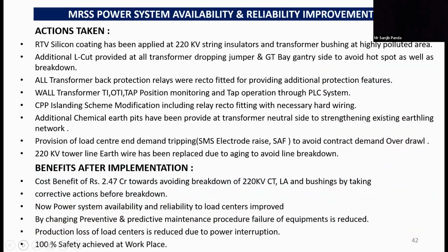So several actions have been taken to mitigate this. Some improvement measures have been taken, like RTV silicon coating has been applied on the insulators of the 220 kV, and some modifications have been done, like L cut has been provided in the dropping jumper and GT bay gantry side. Some backup protection relays have been retrofitted, and several measures have been taken, as you can see, which has given us cost benefits by reducing downtime, and availability has yielded around 2.47 crores over the year, and availability and reliability has been improved, and obviously 100% safety is being achieved due to this measure. Thank you. Next, ma'am.